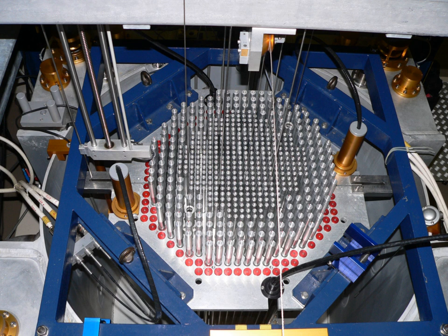The amount of energy extracted from nuclear fuel is called its burn-up, which is expressed in terms of the heat energy produced per initial unit of fuel weight. Burn-up is commonly expressed as megawatt days thermal per metric ton of initial heavy metal.